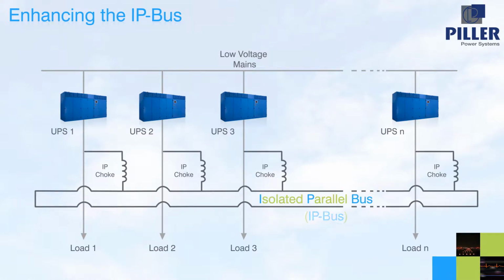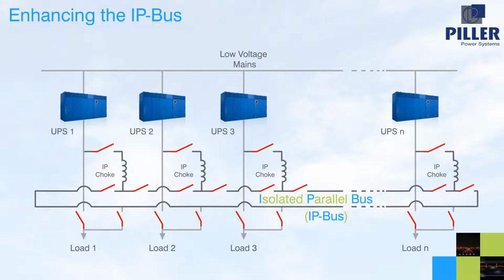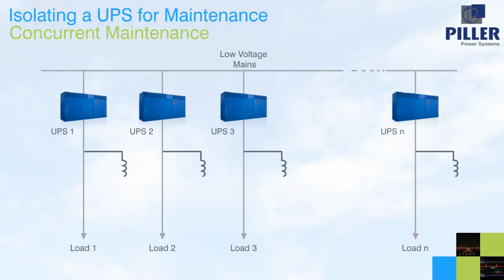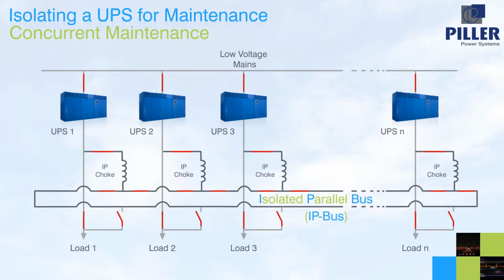These features and the basic IP system functionality can all be realized with just one circuit breaker at the IP choke. Enhancements, if desired, can be made to both the functionality and the maintainability by the addition of further breakers. Isolating any UPS for maintenance purposes is a simple and risk-free operation. The breaker between the load and the IP bus is closed, so that the load can be directly supported from the ring. Then, the breaker from the UPS is opened in a closed transition, which is totally secure for the load. Finally, the IP choke breaker is opened to provide complete isolation of the UPS unit. It is a simple reversal of this process to reinstate the UPS after maintenance.